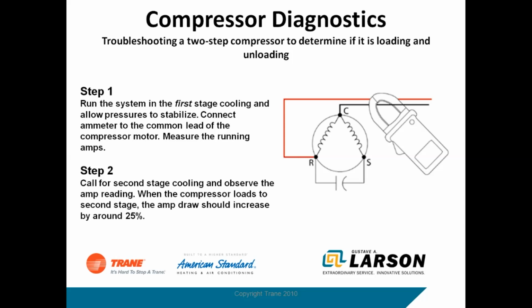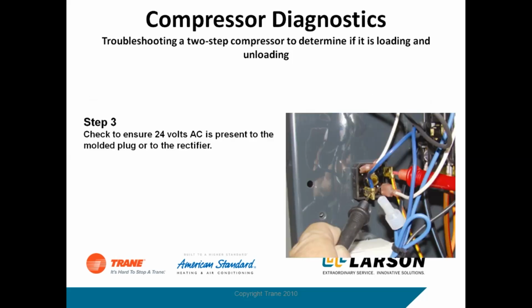So if you want to see if a two-step scroll is working properly, the first thing you do, of course, is put an amp meter on there to make sure that we're drawing proper amperage. And when it goes to second stage, it's going to increase the amp draw maybe 20, 25%. You know, when you're looking at a compressor that's only drawing maybe 15, 18 amps, 25% isn't a lot. It's a couple of amps in a lot of cases. So it's pretty hard to see. But there are some other checks that you can do when you're working on two-step scrolls.